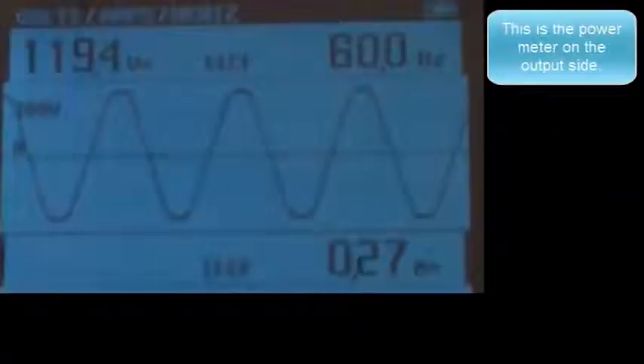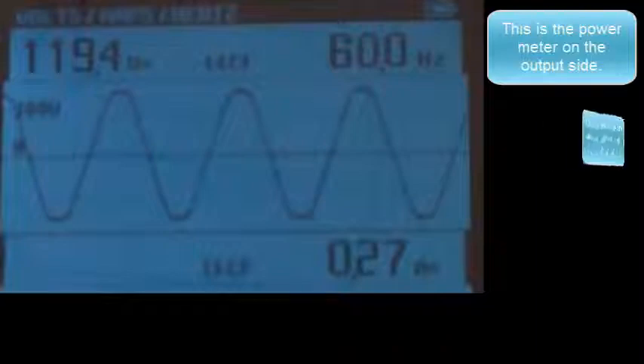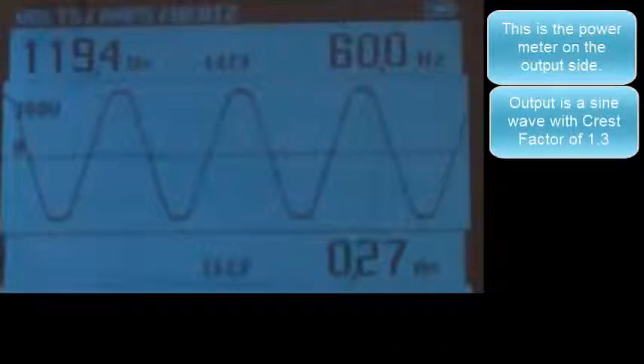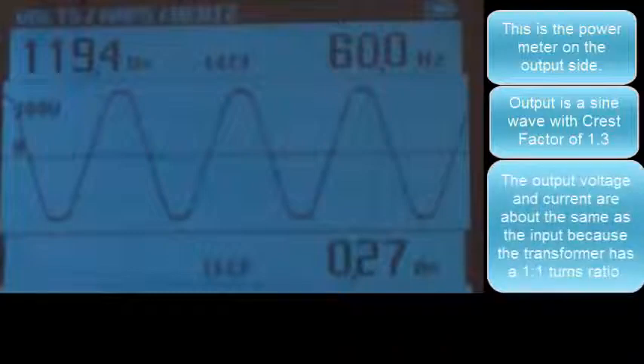This is the power meter on the output side. Output is a sine wave with a crest factor of 1.3. The output voltage and current are about the same as the input because the transformer has a 1 to 1 turns ratio.